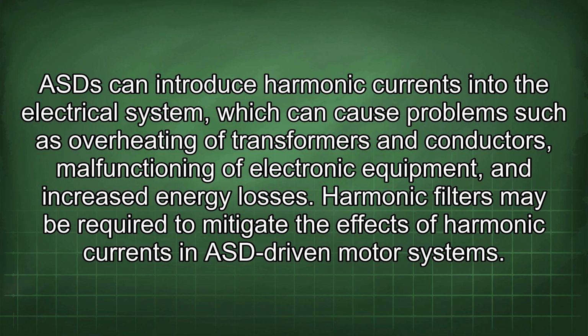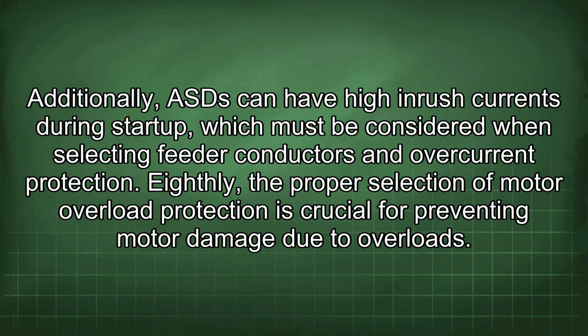Harmonic filters may be required to mitigate the effects of harmonic currents in ASD-driven motor systems. Additionally, ASD can have high inrush currents during startup, which must be considered when selecting feeder conductors and overcurrent protection. Eighthly, the proper selection of motor overload protection is crucial for preventing motor damage due to overloads.